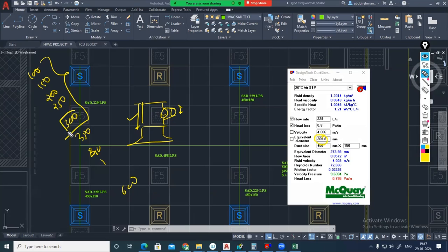300, you should select. If the flexible duct diameter is 300, your plenum height needs to be at least 350, then only can we connect the flexible duct collar there. Another problem, right? So your plenum height will increase.